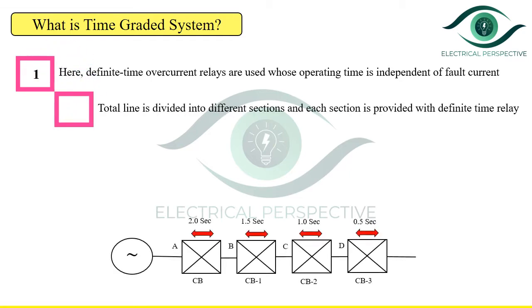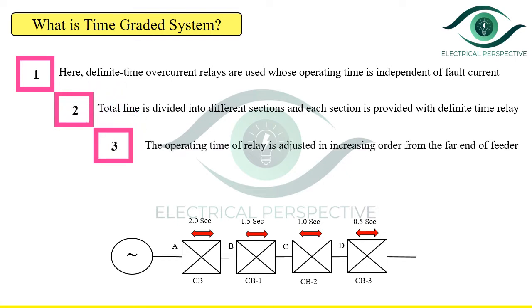We are going to see the application of the time graded protection system applied to a radial feeder, as shown in the figure. The main characteristic of the radial system is that power can flow only in one direction, that is from the generator or supply end to the load end. The total line is divided into different sections and each section is provided with a definite time relay.